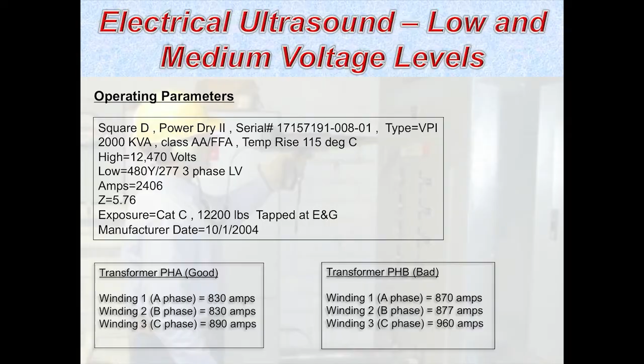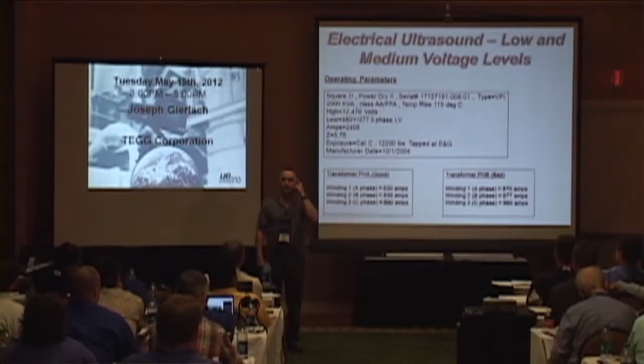You asked about the load levels, listed here on the bottom. This is the good unit, and the suspect, or bad unit, on the right-hand side - fairly balanced loads, with a full load rating of 2,400 amps. On the good transformer, about 830 amps on A and B phase, with some imbalance on C phase at 890 amps. On the suspect unit, 870, 877 amps, and 960 - is that fairly balanced between the two units? There's some difference, but it's pretty close. So knowing you have relatively similar operating conditions, should the units both look the same thermally and sound the same ultrasonically?